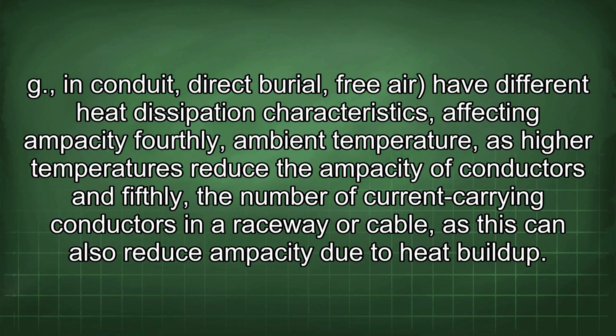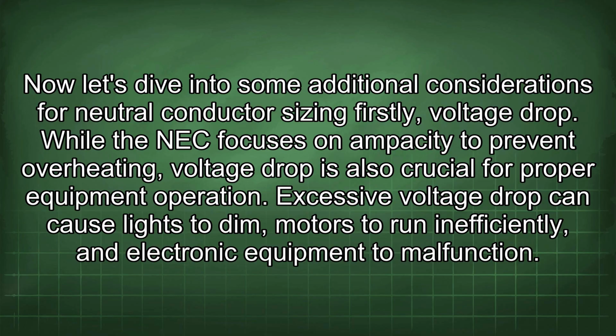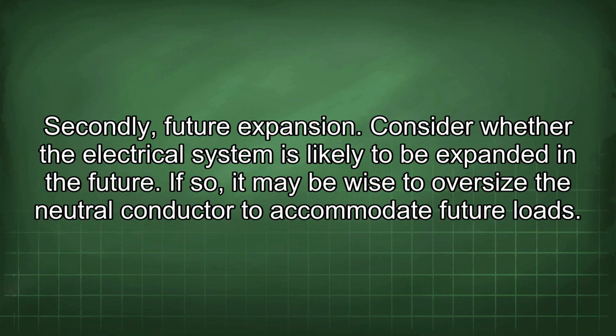Now let's dive into some additional considerations for neutral conductor sizing. Firstly, voltage drop. While the NEC focuses on ampacity to prevent overheating, voltage drop is also crucial for proper equipment operation. Excessive voltage drop can cause lights to dim, motors to run inefficiently, and electronic equipment to malfunction. Secondly, future expansion. Consider whether the electrical system is likely to be expanded in the future. If so, it may be wise to oversize the neutral conductor to accommodate future loads.